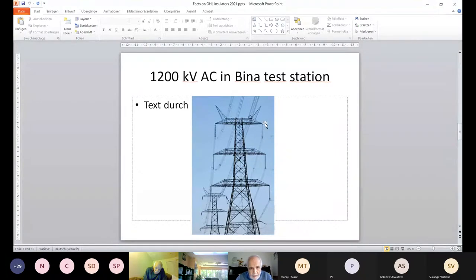Composite insulators you can make as long as you like. Porcelain insulators, cap and pin, of course only caps, but also long rods, you cannot make longer than about 1 meter, maybe 150. So you need more members in the string, which is not serious, but has some issues. Here you see a nice comparison, and also composite tends to be a little shorter. So don't think that I am biased against composite.